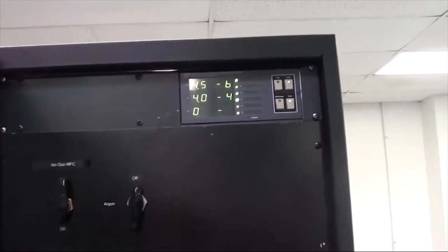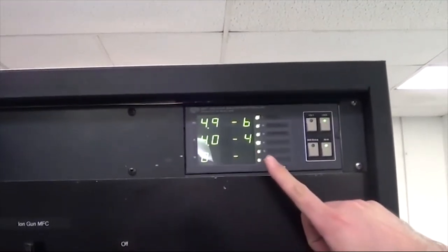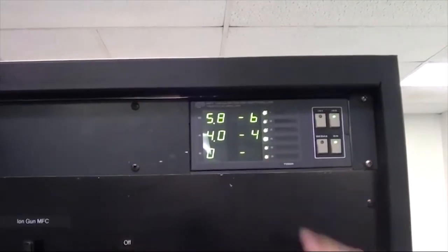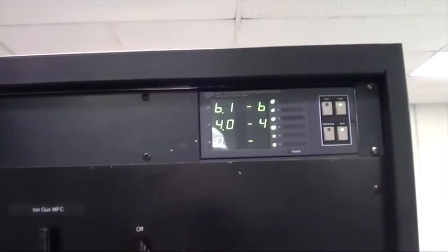So, one issue that we also found is when turning on the dome controller, you press the button, but you'll see a rise in pressure, indicating that there's some small leak on the feed through for the dome.